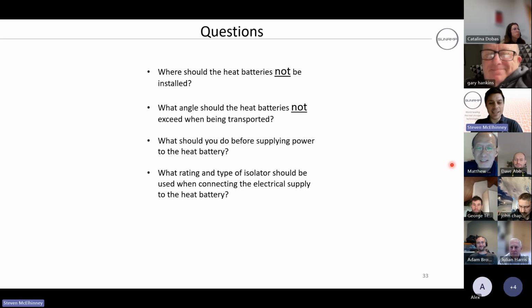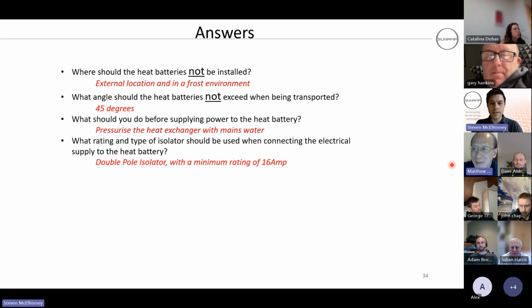What rating and type of isolator should be used when connecting the electrical supply to the heat battery? 20 amp double pole. Yeah. Yes, I'll give you that. I'll give it half a point for the double pole. 20 amp. I mean, the minimum rating is 16 amp.